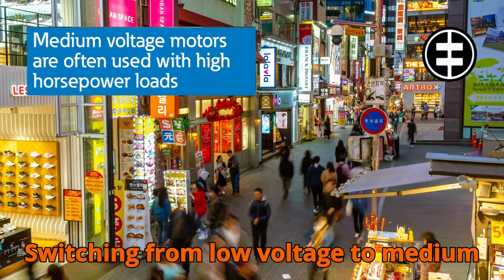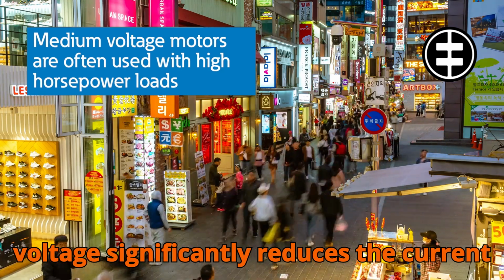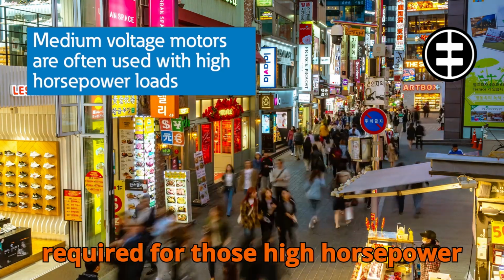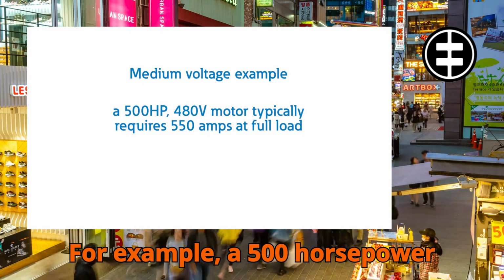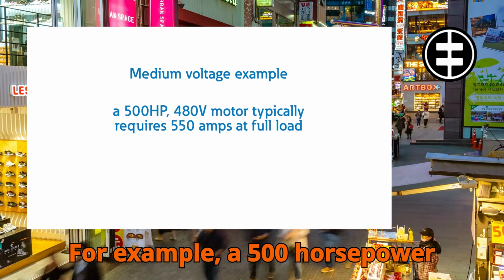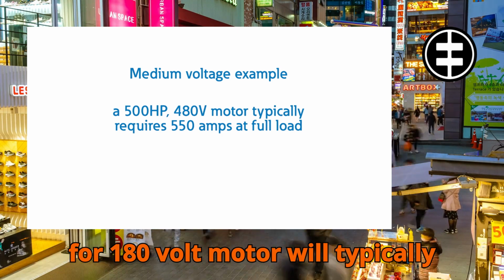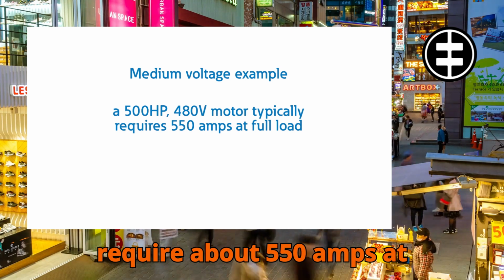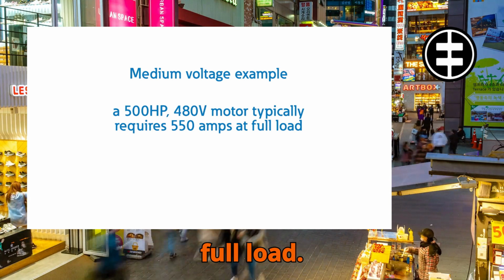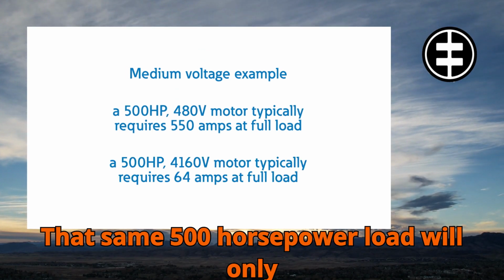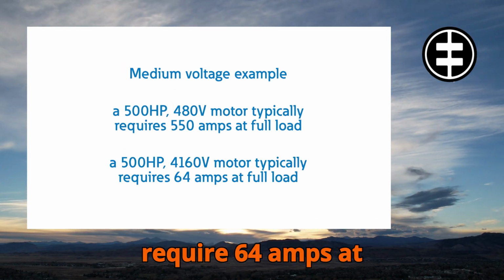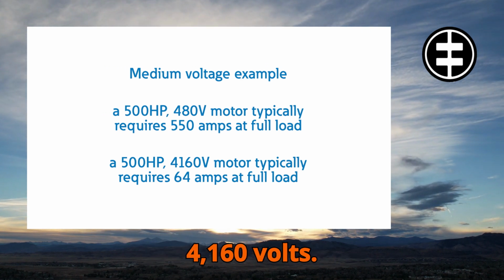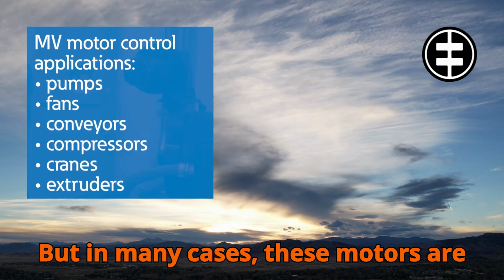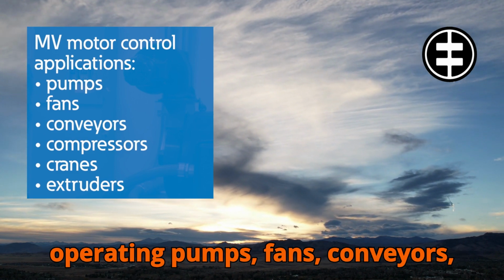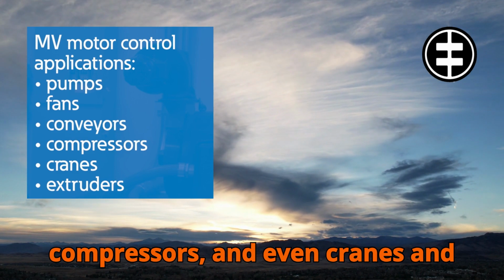Switching from low voltage to medium voltage significantly reduces the current required for those high horsepower motors. For example, a 500 horsepower 480 volt motor will typically require about 550 amps at full load. That same 500 horsepower load will only require 64 amps at 4,160 volts. But in many cases, these motors are operating pumps, fans, conveyors, compressors, and even cranes and extruders.